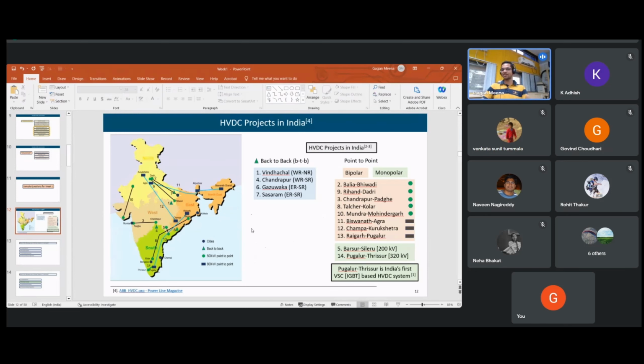The advantage of bipolar is that if there is a fault in one of the conductors, we are still able to serve half of the load through the other conductor. But this flexibility is not there in monopolar. If there is a fault on the conductor in the monopolar case, we will not be able to continue giving supply to the load. But since it is simple and economical, we went for monopolar, and this monopolar was built only in 1989. After that, we didn't go for monopolar. Yes, bipolar is much better.